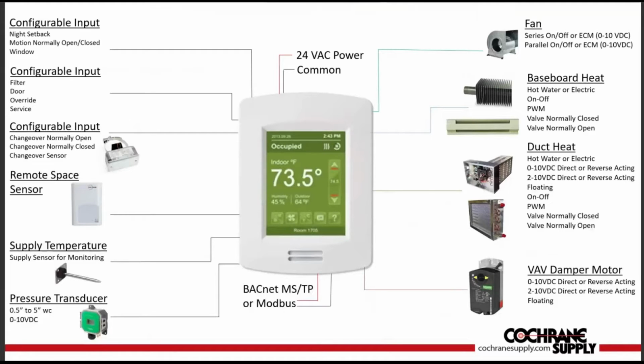Here's a look at all the options that are available on the 8250 series room controller out of the box. Notice this controller has 7 inputs and 9 outputs that are used based upon the way in which the installer configures the room controller. Inputs can be configured for operations like window and door switches, dirty filter, or general service notifications. Changeover sensor, either a contact closure or resistive temperature sensor, can be connected for VVT zone control applications. A remote space temperature sensor can be connected, and supply air sensor can be added for monitoring purposes. There's also an input for a pressure transducer for VAV applications that use a flow ring.